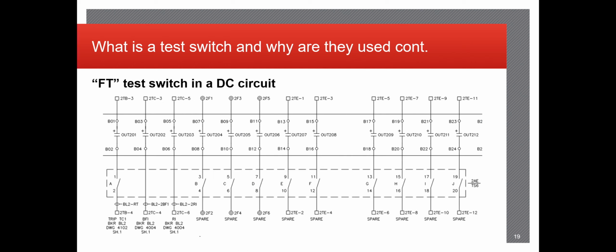So these are what the test switches look like on a DC circuit schematic. This is what we will look at when we're functionally testing the relay circuits. You can see they're identified by A, B, C, D, etc., as well as the numbers. The numbers indicate which side of the relay test switch should be going to where. Usually the odd numbers at the top will run directly to the relay, because it's more common than not that the relay will be installed above the test switches, as well as that's the easiest way to isolate them and understand that it's going to be isolated properly as well.